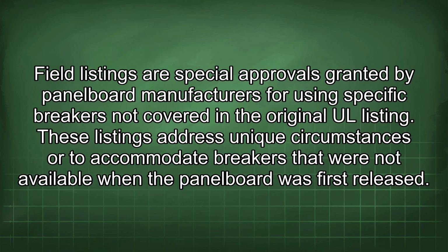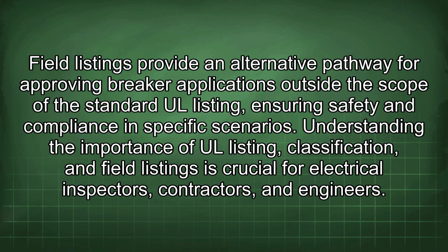Field listings are special approvals granted by panel board manufacturers for using specific breakers not covered in the original UL listing. These listings address unique circumstances or accommodate breakers that were not available when the panel board was first released. Field listings provide an alternative pathway for approving breaker applications outside the scope of the standard UL listing, ensuring safety and compliance in specific scenarios.